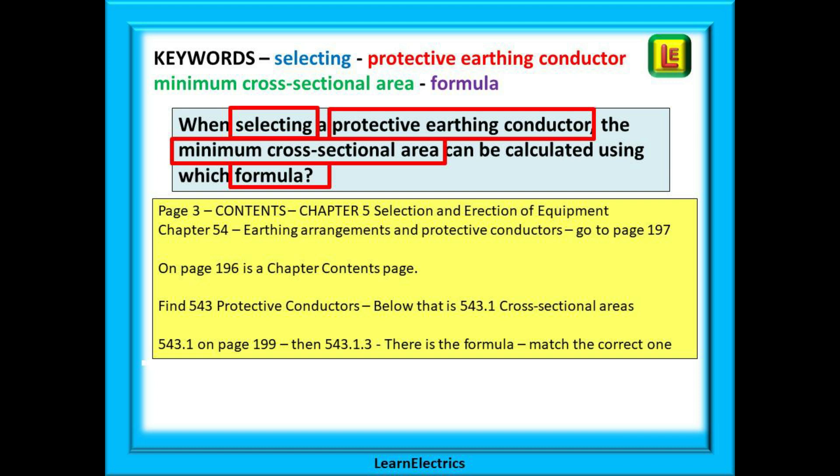Chapter 5 says 'Selection and Erection of Equipment', and just below is Chapter 54 — Earthing Arrangements and Protective Conductors. Go to page 197. On the opposite page, page 196, is a chapter contents page. Find 543 — Protective Conductors, and below that is 543.1 — Cross-Sectional Areas. We can find regulation 543.1 on page 199, and then sub-regulation 543.1.3, and there is the formula that we need.